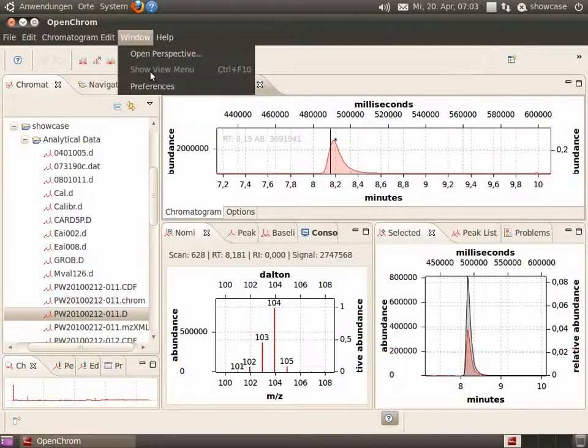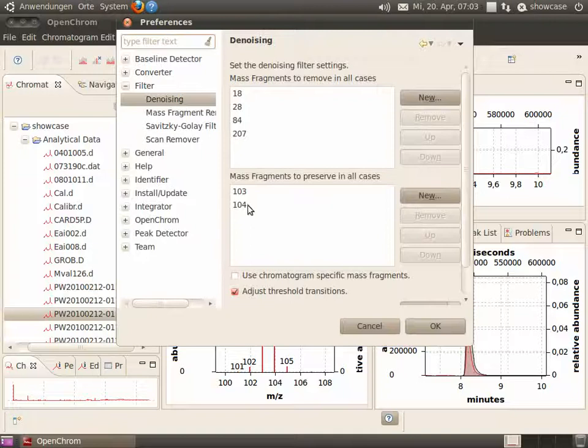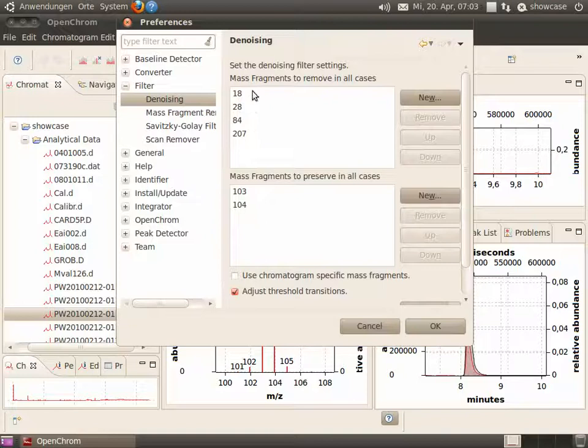Okay, let's denoise the chromatogram but we want to preserve the mass fragments 103 and 104. Let's go to the filter settings and select the mass fragments that shall be preserved. Further on, you can select mass fragments that shall be removed in all cases.